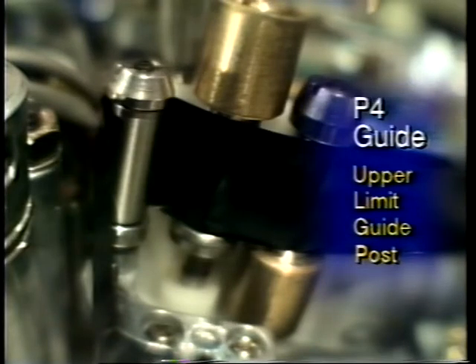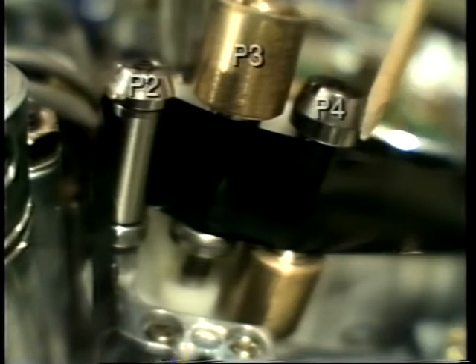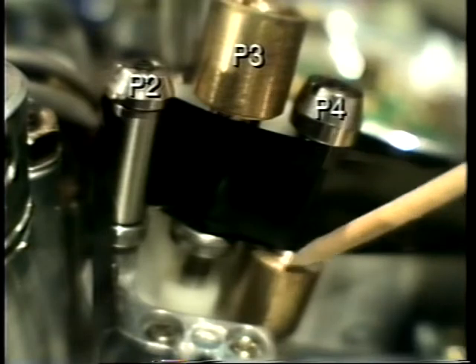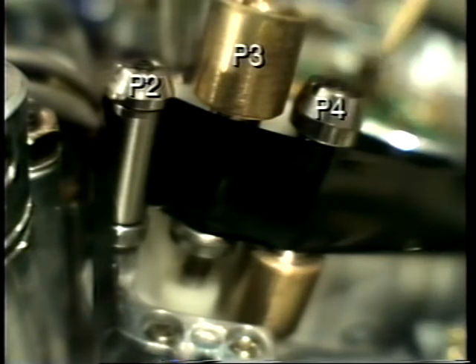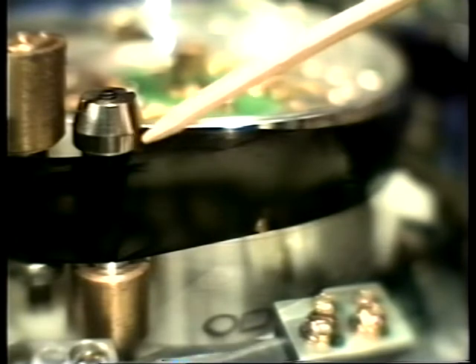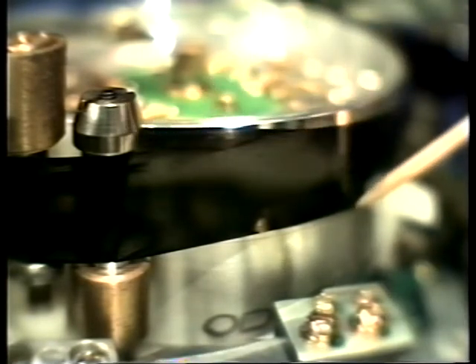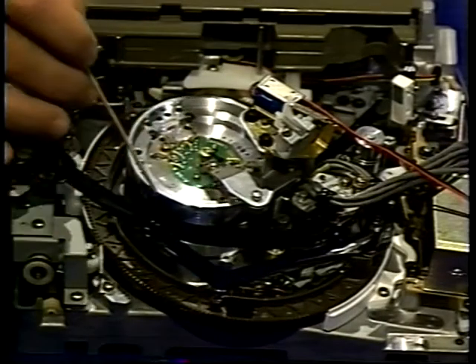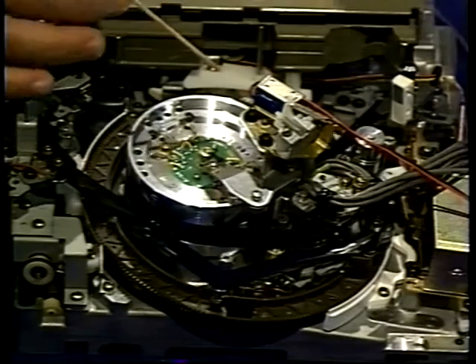P4, an upper limit guide post, is the last guide that sets a limit before the tape enters the lower guide of the lower drum. Move P3 and P4 out of the way when adjusting the height of P2 to eliminate their influence on the tape. Look at the tape path between P4 and the lower limit. Check that there is no tape curl at P4, and no tape deformation at the entrance to the lower guide. Note that the lower drum is the lower reference.